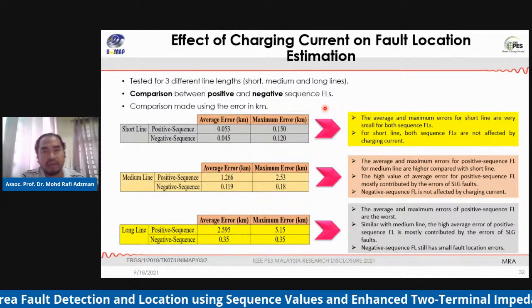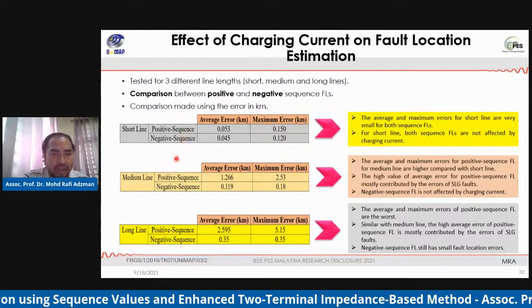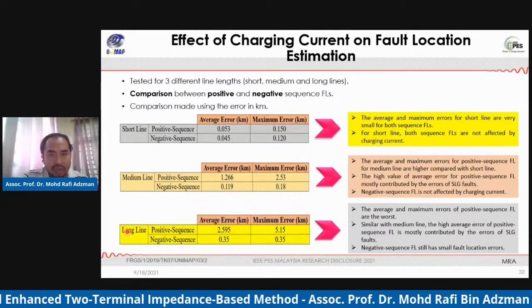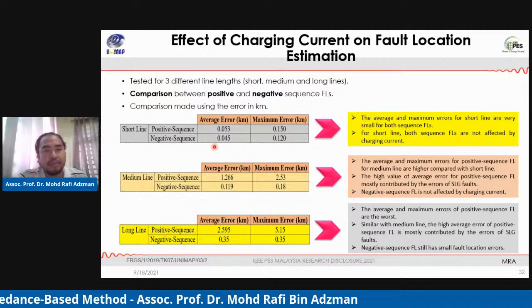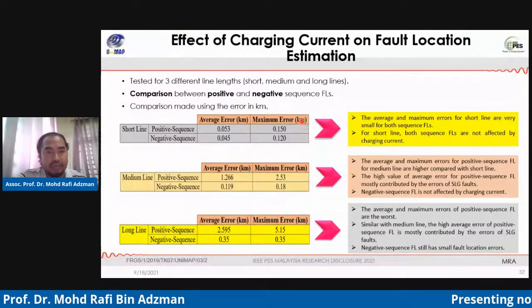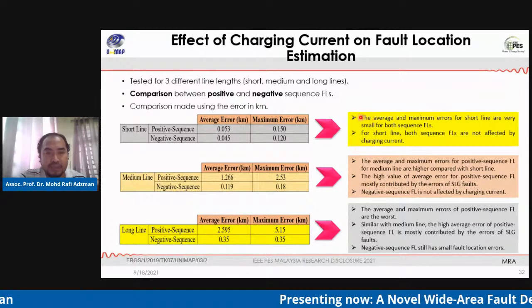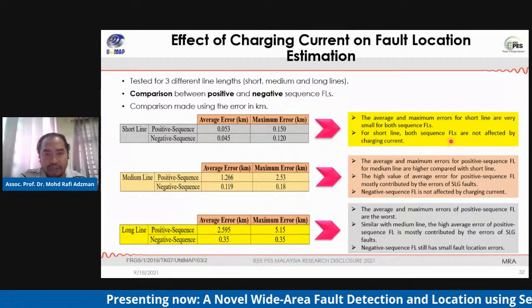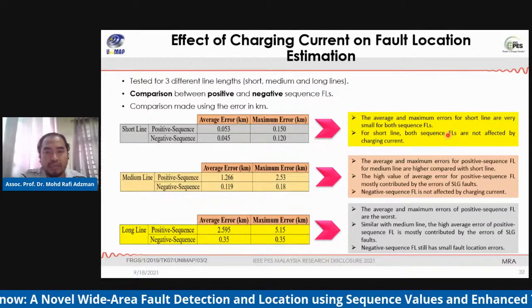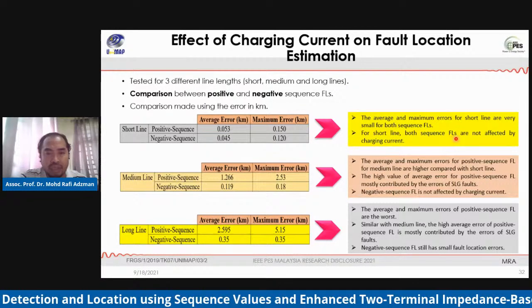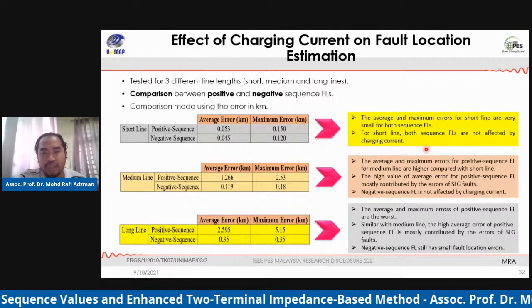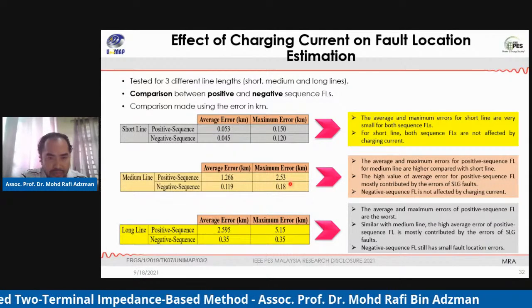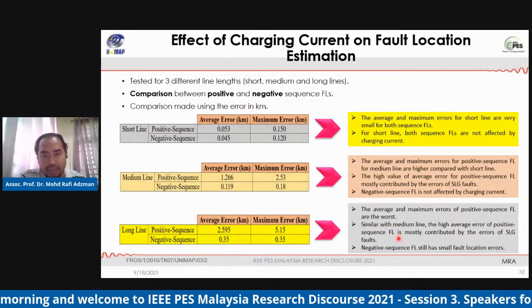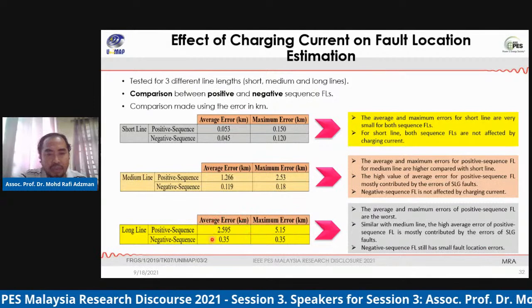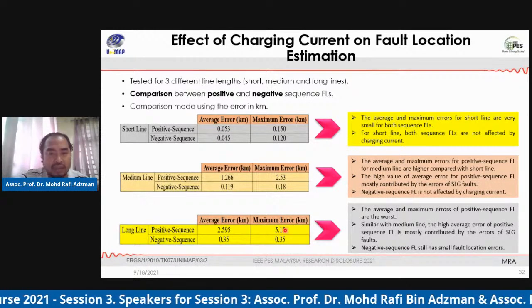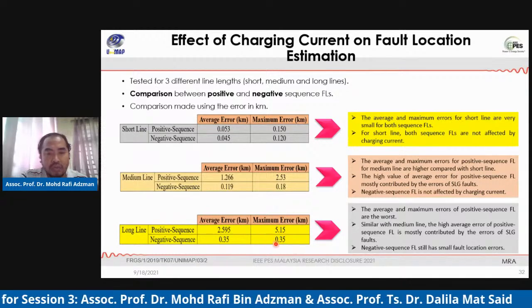For the effect of the charging current on fault location estimation, we tested 3 different line lengths: short, medium, and long. Here we compare the positive and negative sequence fault locations using the error in kilometers. For short lines, the average and maximum errors are very small for both the positive and negative sequence fault location techniques, so both are not affected by charging currents. However, on long lines, the average and maximum error for positive sequence fault location is higher compared to the negative sequence. In this case, the negative sequence fault location still has a small fault location error.